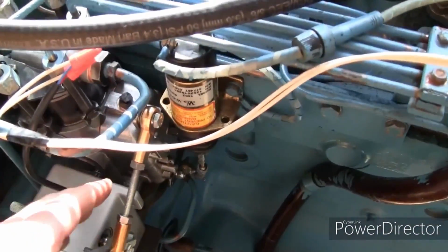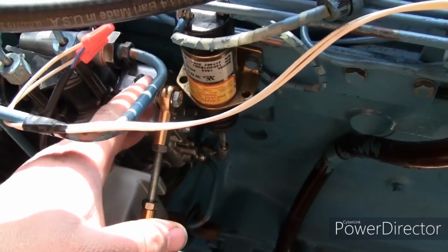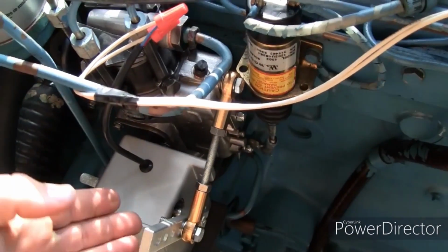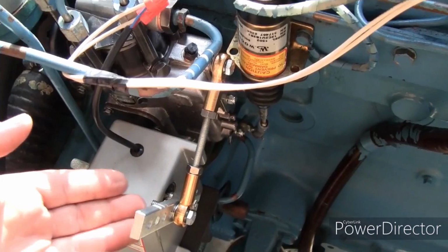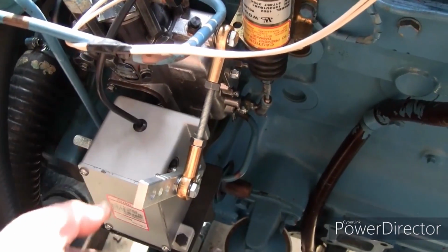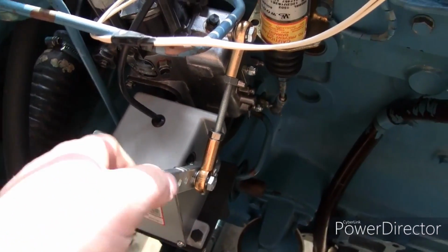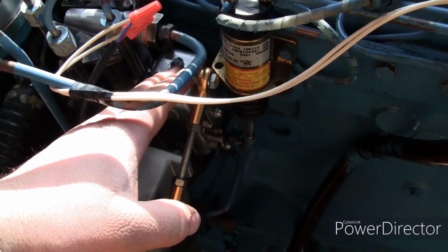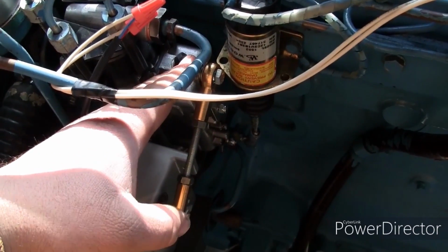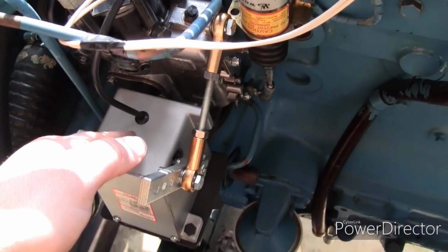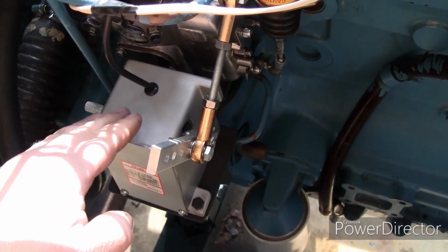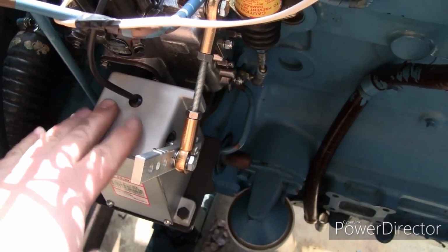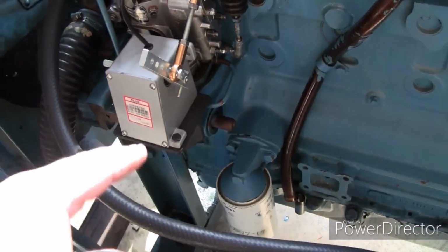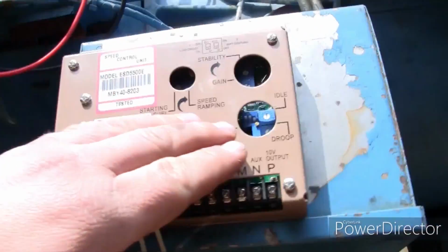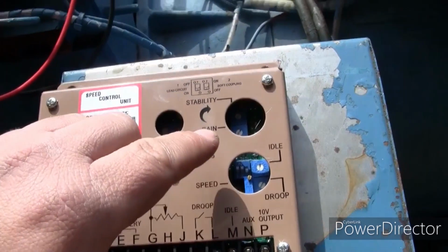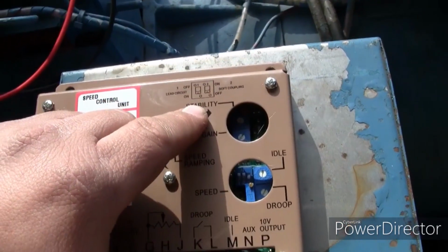So right now, I've got the linkage set to give us about 58 hertz. With the actuator at the no fuel position, the throttle lever set at about 58 hertz, we're going to adjust the governor up to just over 60 hertz, like 60.1 or so, and we'll go from there. And we'll go through the speed, gain, and stability settings.